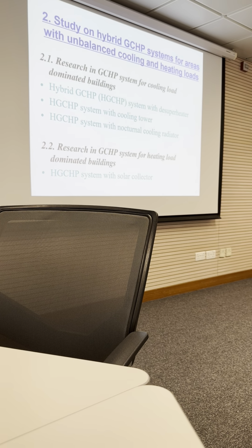Then we studied another topic called the hybrid system. We want to solve the energy imbalance problem, because we inject too much energy into the ground, and we think we may solve the problem partially. For example, we can use a hybrid ground coupled heat pump system for areas with unbalanced cooling and heating load, as is typical in Hong Kong and the Guangdong area, because we nearly don't have winter. We don't need heating.